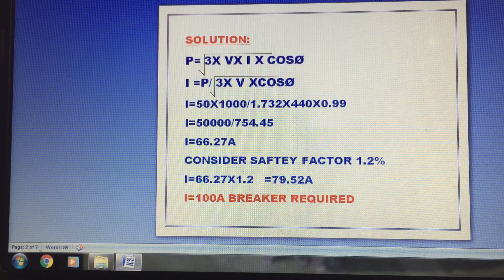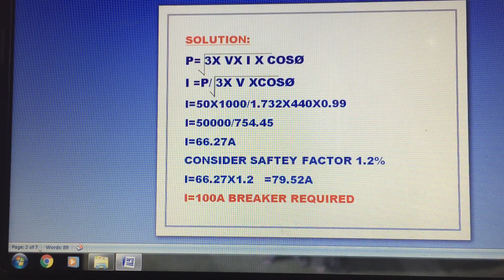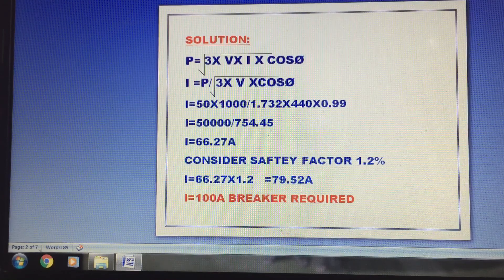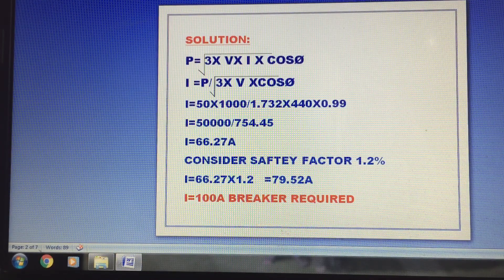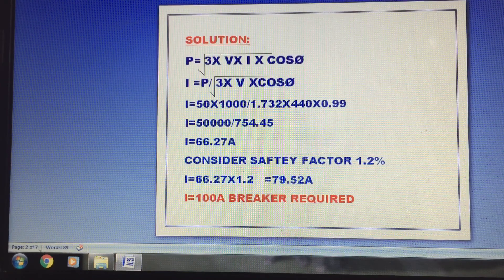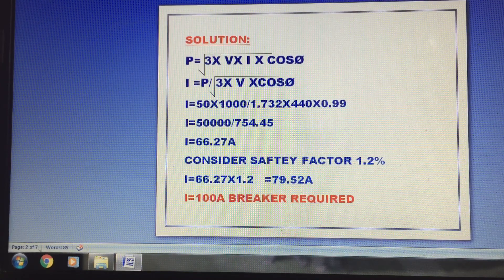We need to find current I. Current is unknown. So I is equal to P divided by root 3 times V times cosφ. Power P is 50 kilowatt, which is 50 into 1000 watts.